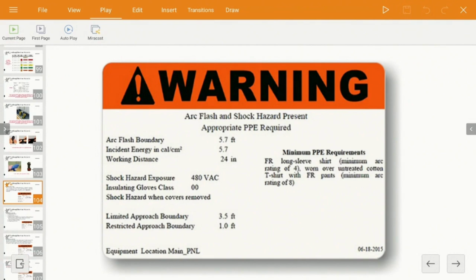And if you look here, it says, what's that? Yes, 5.7 calories per centimeter squared. That lighter example, times that by 5.7. That's how bad the arc flash is going to be for that equipment that this label's on. And it tells you your boundaries for shock, tells you your arc flash boundary.